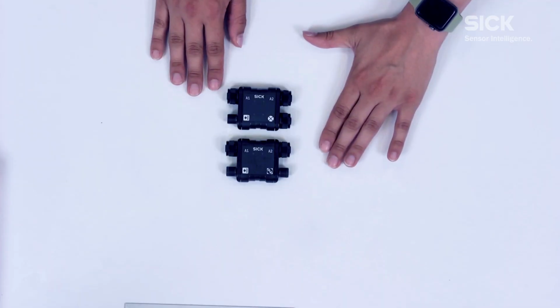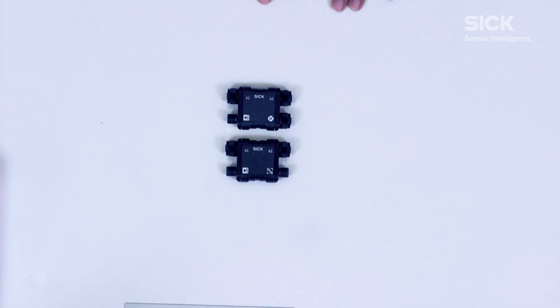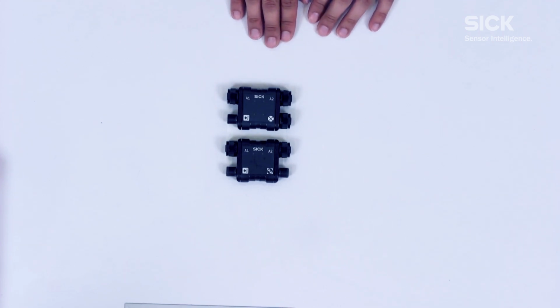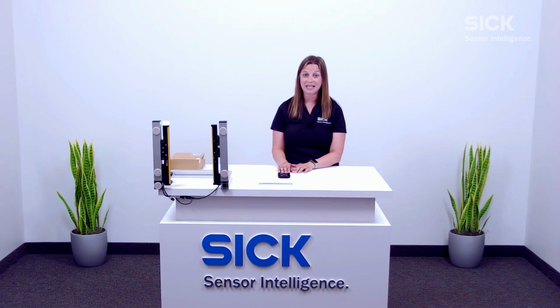Here I have our two different muting nodes that we have at SICK. As you can see here, they are labeled with A1 and A2. That's where we typically connect our muting sensor inputs, so we can take in those signals locally at the light curtain and have only one cable running back to our safety controller. This reduces the need to program within your safety PLC or safety controller. It reduces I/O and really makes for easy integration.